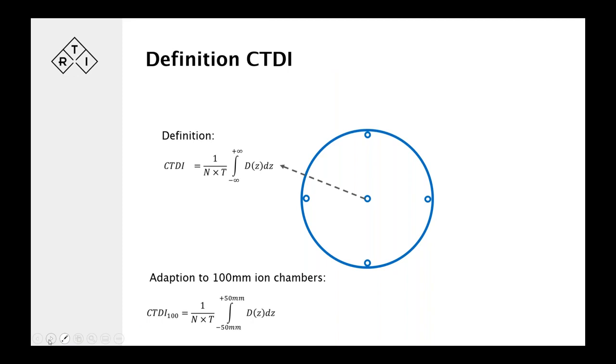All right. But then we have other challenges. We won't go into those today, but it touches the subject that we're on. When you have collimations and beam widths larger than 40 millimeters, you have a problem with the formula, because the scatter generated will go beyond plus and minus 50 millimeters inside the phantom.